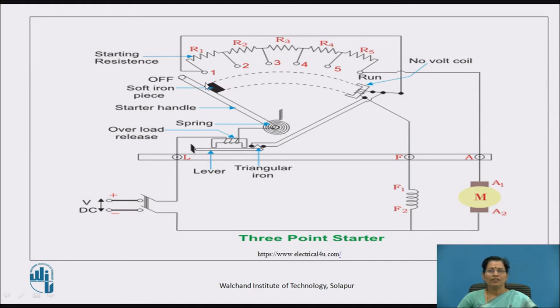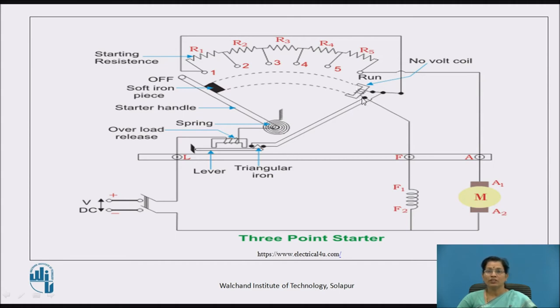When we move this handle to the first position, the total resistance is connected in series with the armature. Due to this series resistance, we can limit the starting current. Then afterwards, we move this handle from first to second, second to third, and so on, up to the run position. When current flows through the no-volt coil, it creates a magnetic field, and this arm is held by the no-volt coil because a magnetic material is connected here, and the overload coil is connected here.